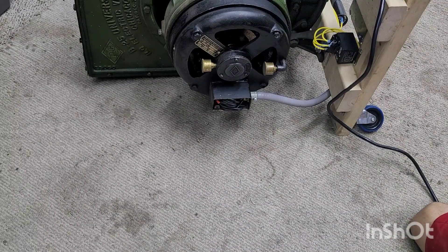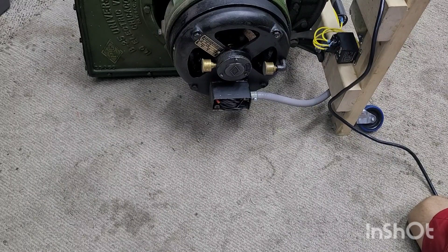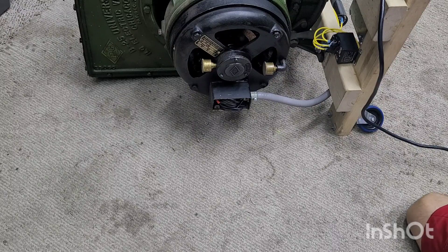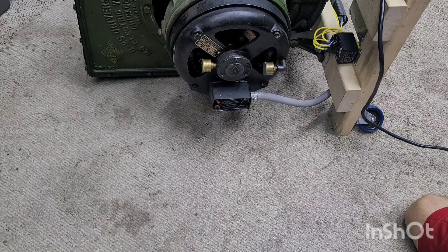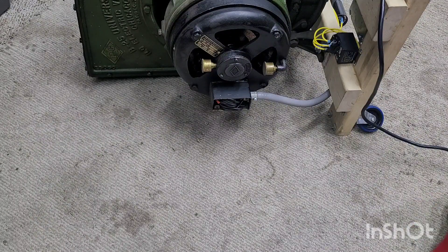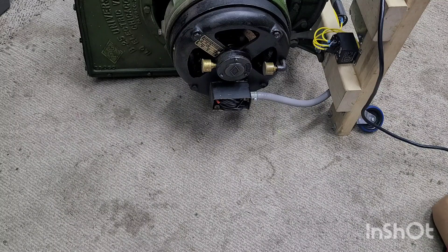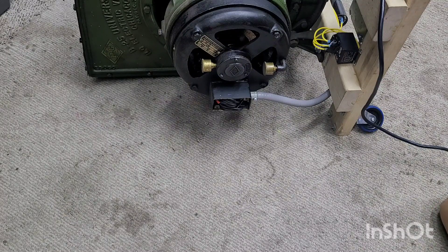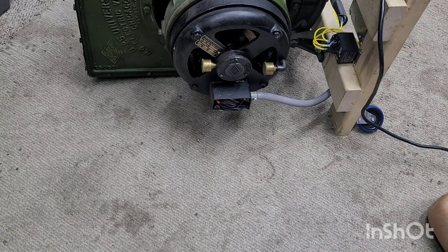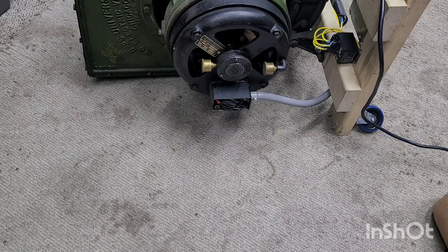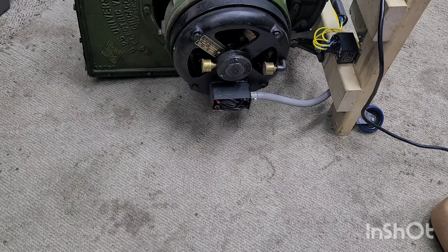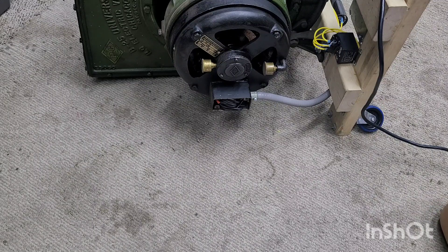For this ILG B25 blower, the motor is a three-phase motor with a voltage on the tag of 220 volts. The application this came out of was used in a school and was wired for three-phase 220 volts. The building was built in 1932, so at that time 220 was common. Now you hear 230, 240, 250 even used instead of 220, but at that time that was the standard.